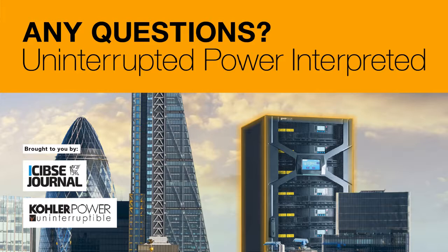Especially with modular, we can hot swap it. So when we get a call with a modular system, we determine if it's a module or not, and we take it with us. And then we take the problem off site, so that mean time to repair is very quick. If it's a standalone unit, we have to obviously get to site and then determine what the problem is, and then take it apart and fix it.